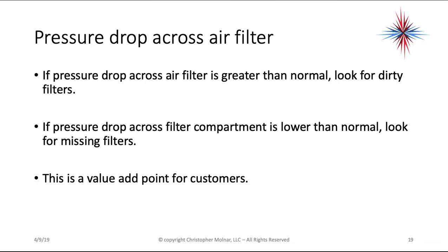If the pressure drop across an air filter is greater than normal, look for a dirty filter. If the pressure drop across a filter compartment is lower than normal, look for a missing filter or a filter of lesser quality. This is a value-add point for customers — you can show a customer a before and after and say we fixed a restriction that is affecting the performance of your system.